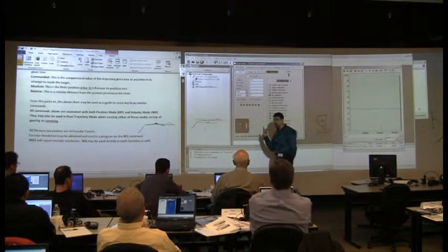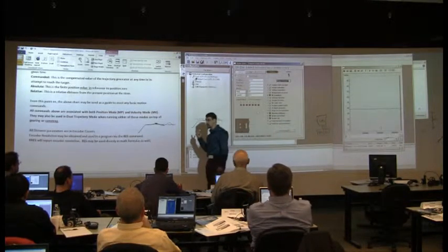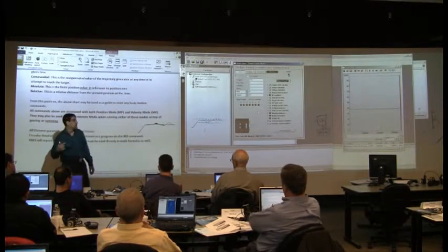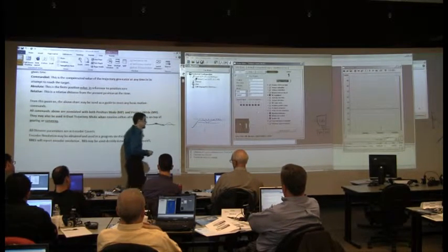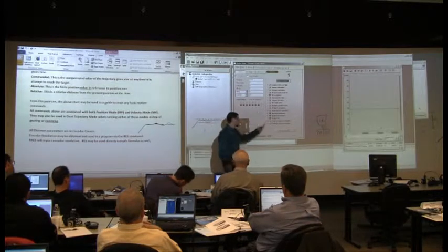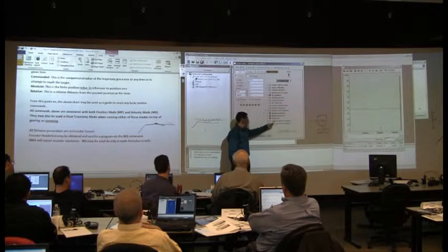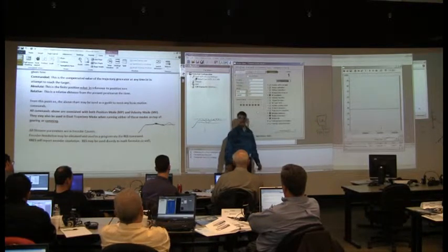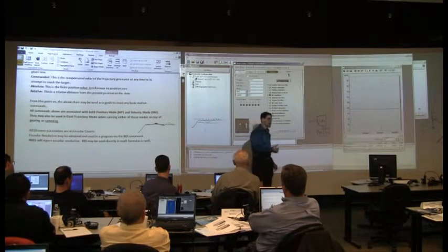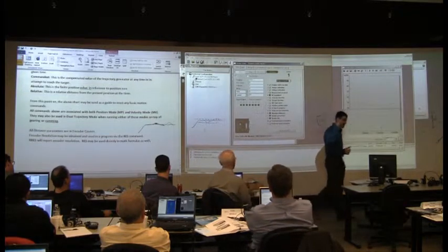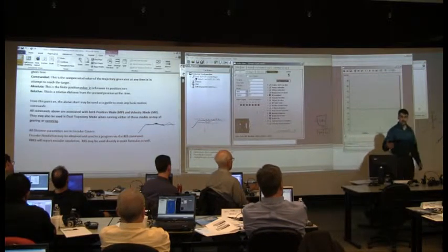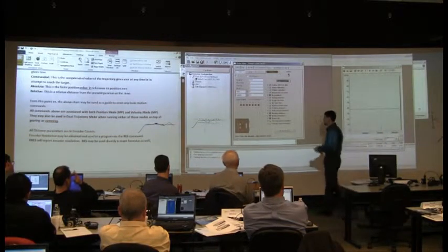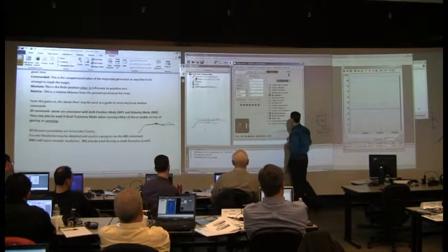That's an internal pin that controls an internal brake if you've got one, or if you redirect the signal to an external pin, it will tell you you're supplying power. Okay? The reason it says brake asserted and on, that means you've got the brake enabled to turn on automatically, and right now it's sending a positive signal to disengage the brake. Because brakes are typically fail-safe, you have to supply power to disengage it and allow the motor to turn. Okay? So that's what this is about.